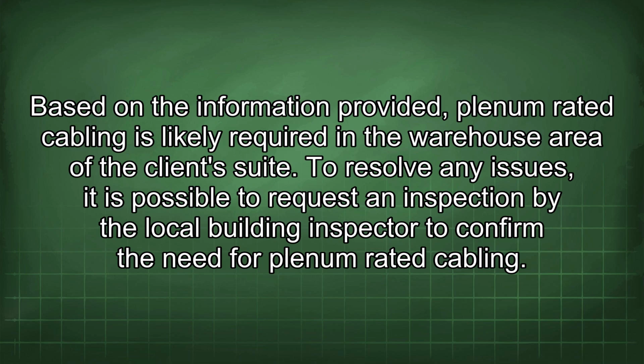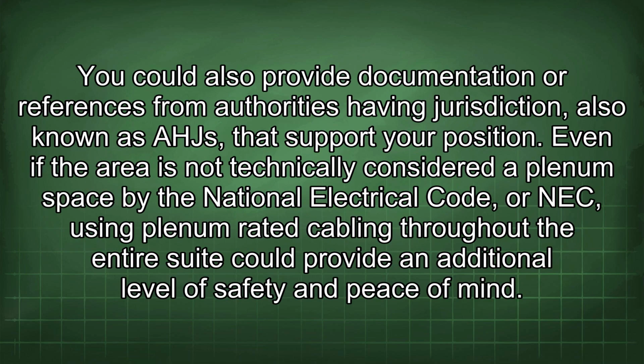Based on the information provided, plenum-rated cabling is likely required in the warehouse area of the client's suite. To resolve any issues, it is possible to request an inspection by the local building inspector to confirm the need for plenum-rated cabling. You could also provide documentation or references from authorities having jurisdiction, also known as AHJ, that support your position. Even if the area is not technically considered a plenum space by the National Electrical Code, or NEC, using plenum-rated cabling throughout the entire suite could provide an additional level of safety and peace of mind.